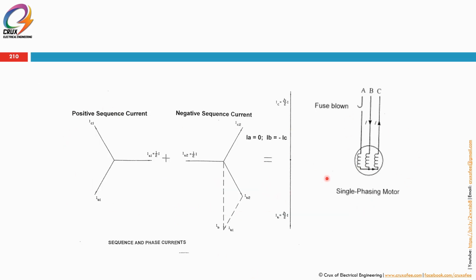So this is a single phasing motor condition. Under this condition, this red phase is blown, so you'll have a single phasing condition where the current is about 1.732 times the rated current. So this is the phase current, not the negative sequence current. So when you measure, it will come up with a negative sequence current, and this can be used as a measurement for tripping the motor based on negative sequence current.